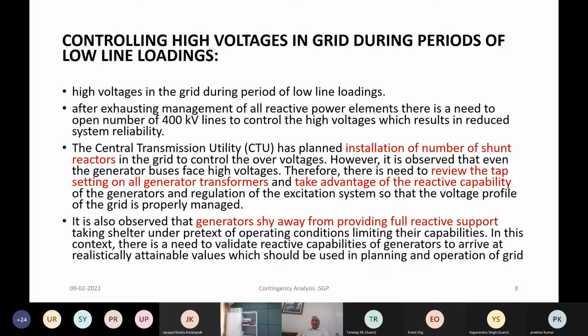But we have to remember that when you open the line, you are actually weakening the network if some contingency happens. That means even at night, if the lines are kept open, as we saw, system stability will get compromised by keeping the lines out. So on one hand you want to control the voltage, but on the other hand you are taking a risk of instability in the system. So this is a balance which has to be very carefully chosen.